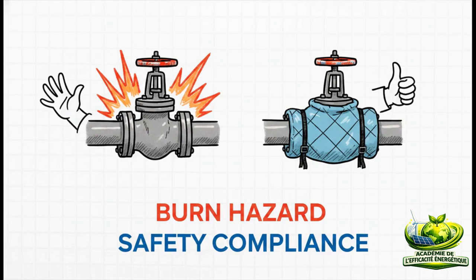But it's not just about the money, right? Exposed valves are a major safety hazard. OSHA compliance actually dictates that heated surfaces need to be 120 degrees Fahrenheit or lower to protect your team from burns. So, an uninsulated 350-degree valve is a massive liability. But wrap it in one of those simple custom jackets, and you instantly drop that surface temperature down to a completely safe 104 degrees. You keep your workers safe, and you stop the bleeding on your utility bill.